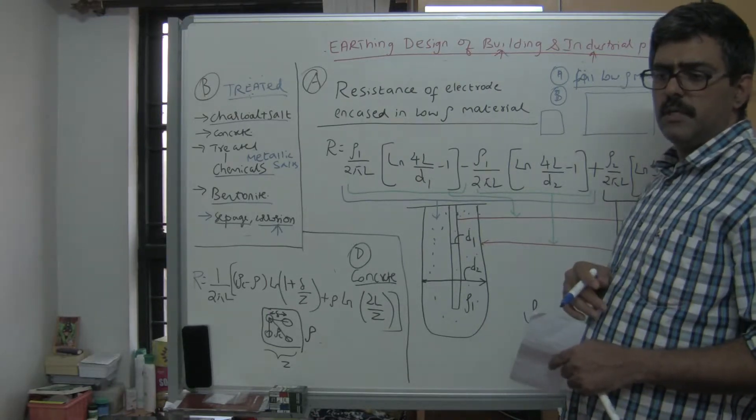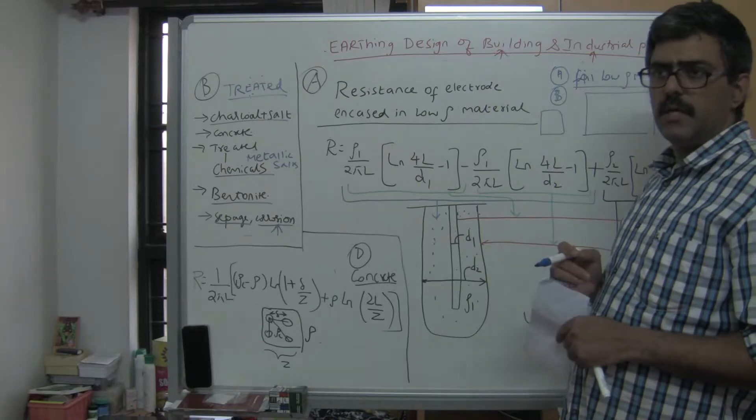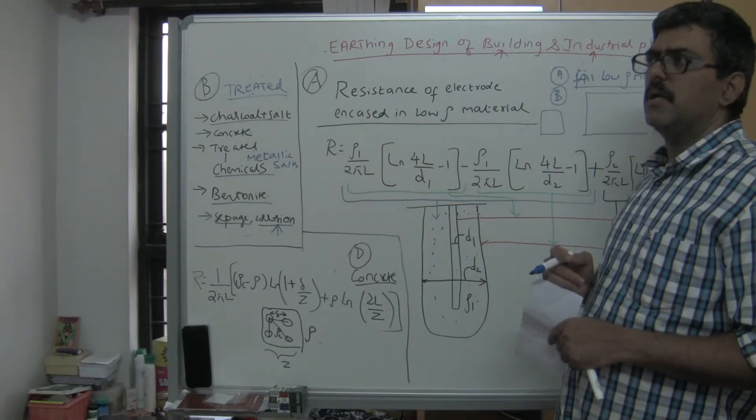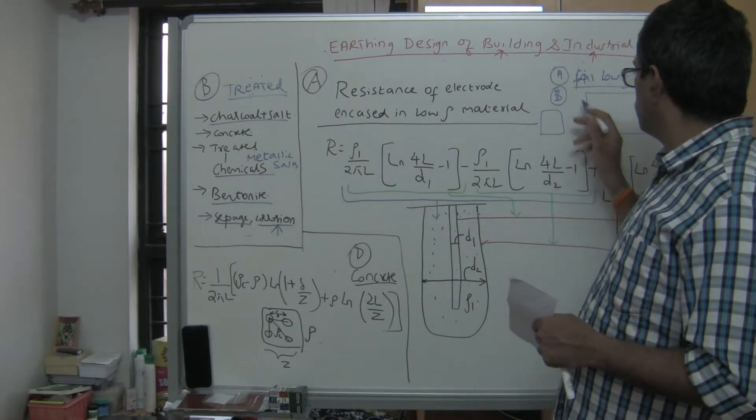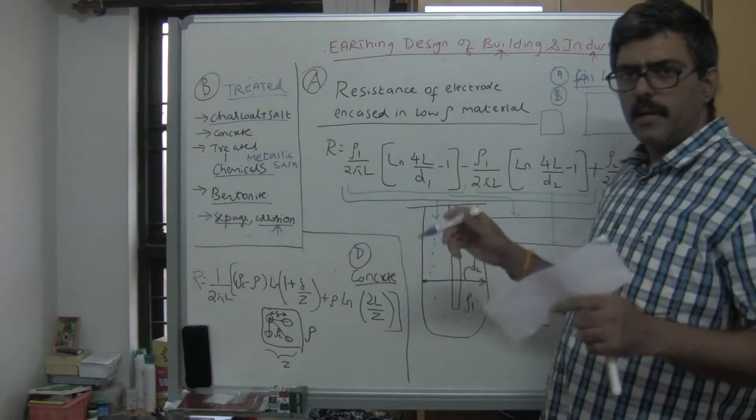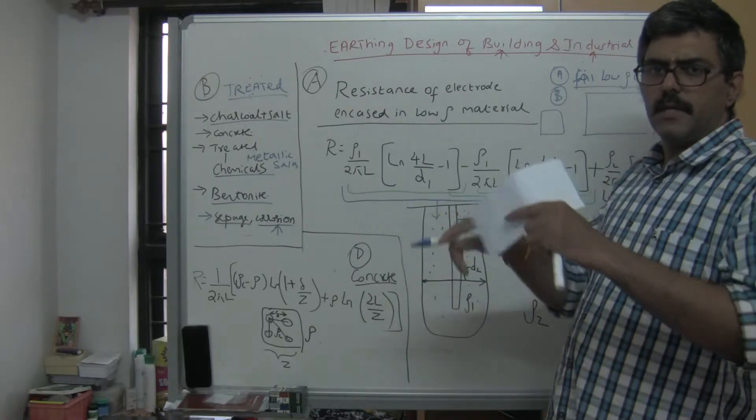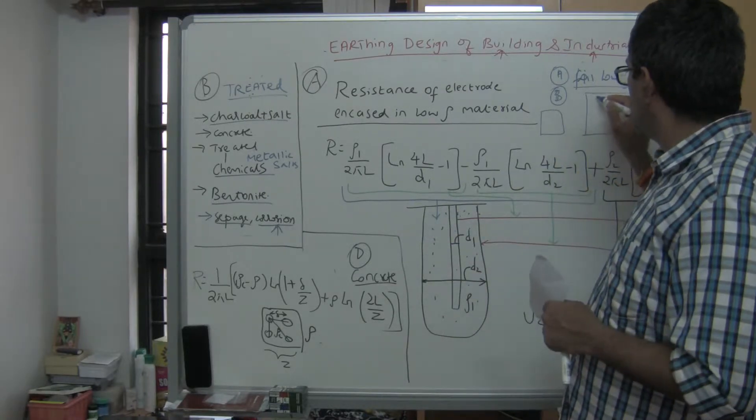But if I have a small substation and the soil resistivity is high, then I cannot achieve a low resistance earth grid. So one option is to go to a remote area where we get a large area and install an earth grid there.